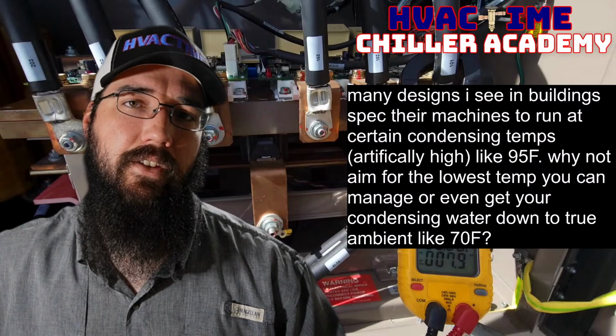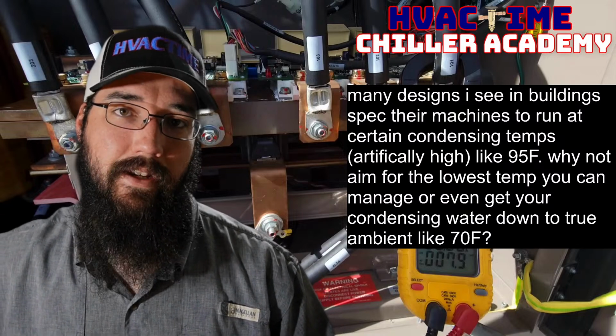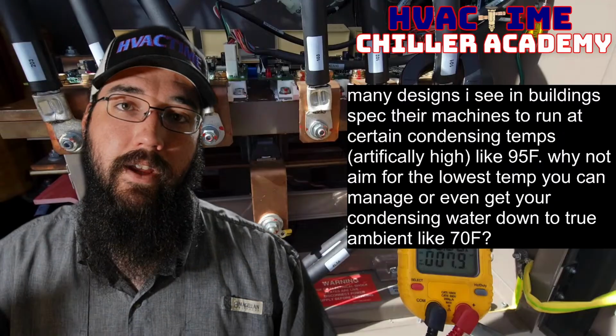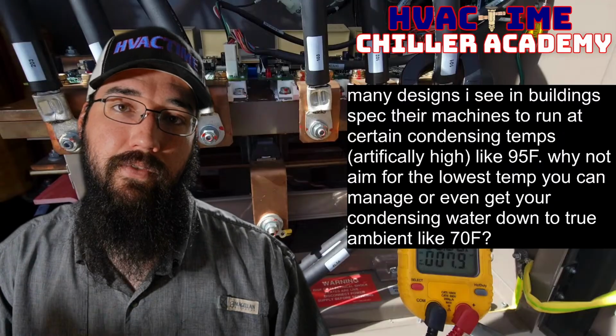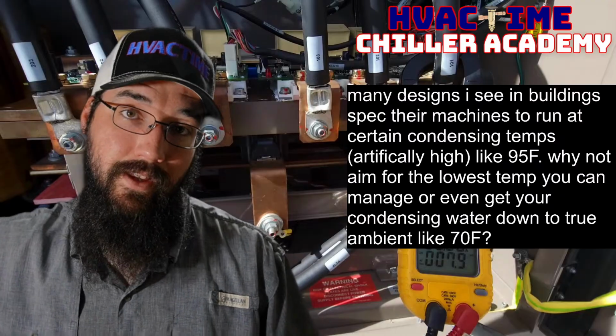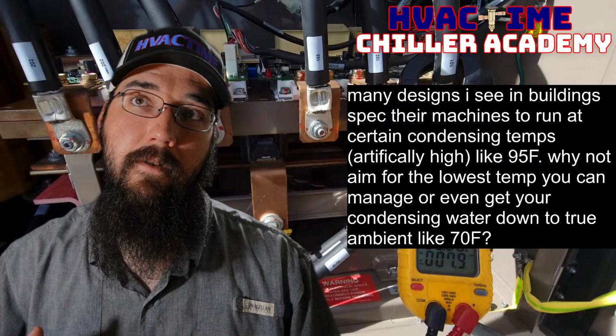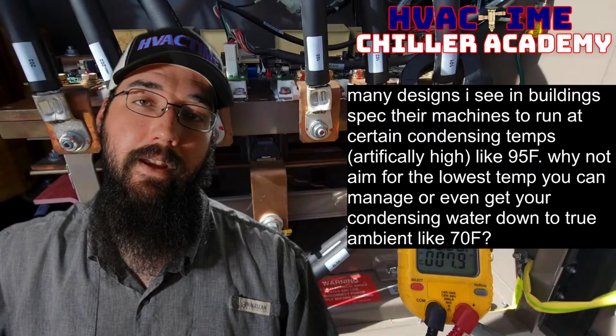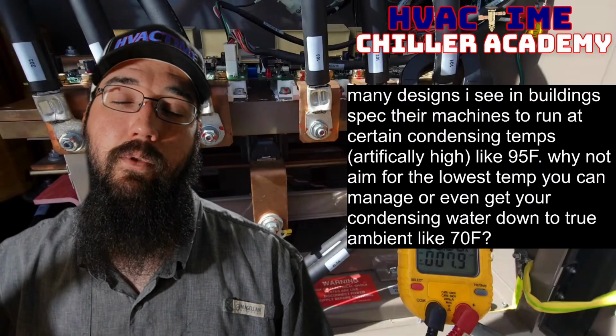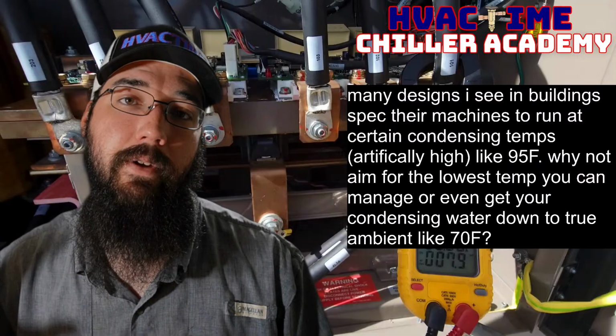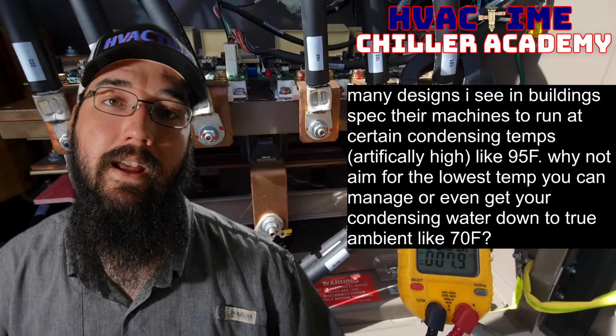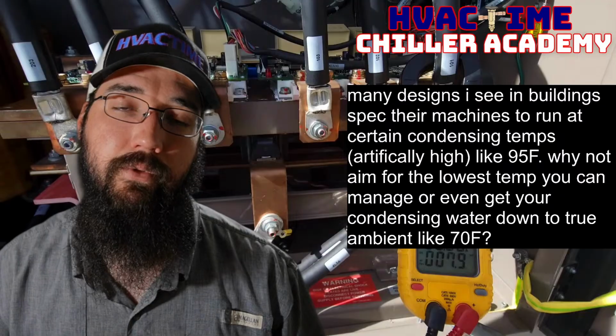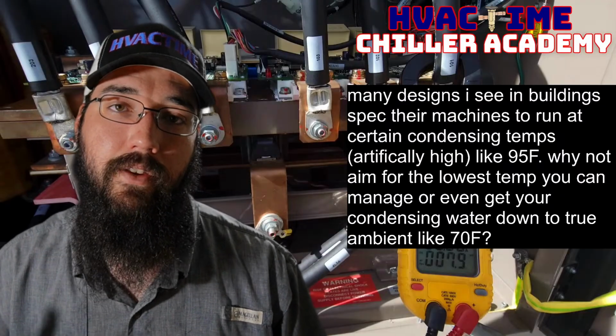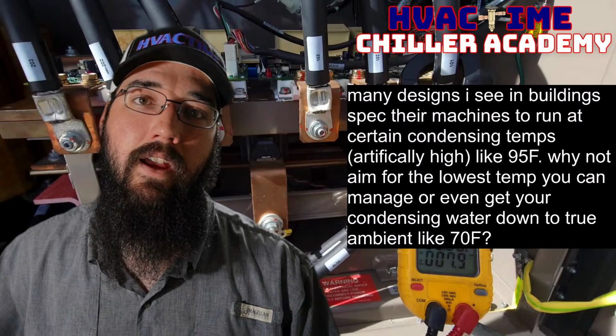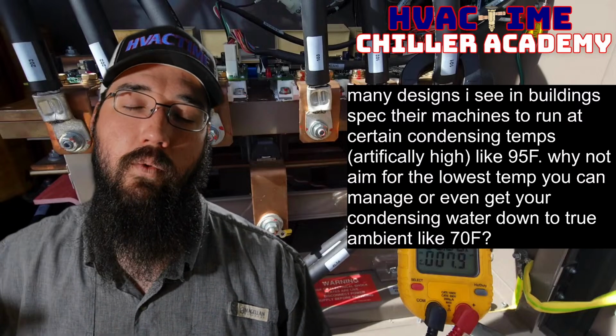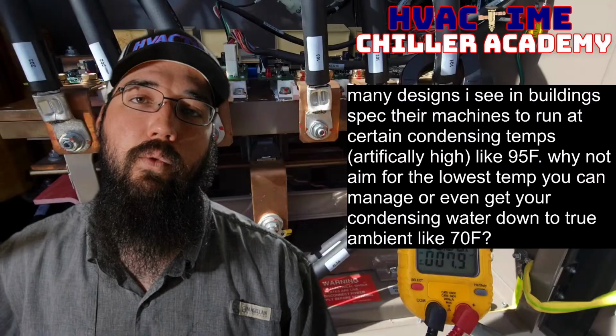I've even gone as high as the maximum that temperature can go is 90. At that point, it'll control that algorithm, wet bulb plus 5 equals your output within this window. Then the control system can vary the fan accordingly. We're not putting any more load on the fan than we absolutely have to make the leaving water set point, which allows us to not have to run the fan at 100% all the time and still get the maximum amount of leaving water temperature, the lowest value we can get for that chiller.